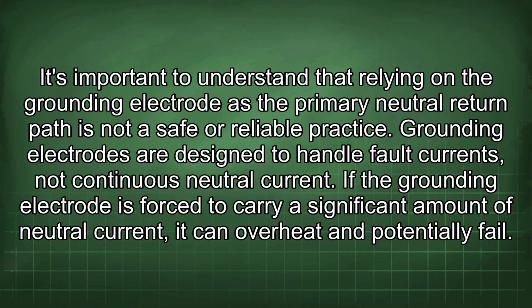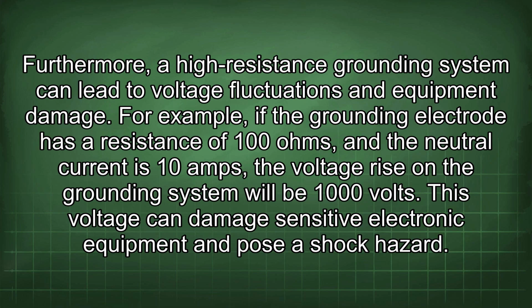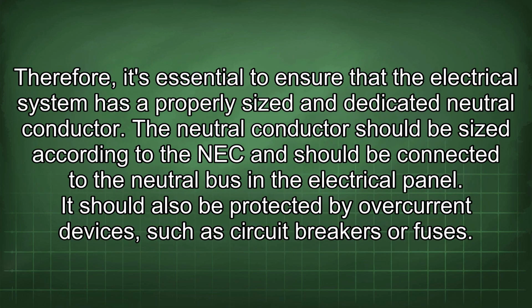If the grounding electrode is forced to carry a significant amount of neutral current, it can overheat and potentially fail. Furthermore, a high-resistance grounding system can lead to voltage fluctuations and equipment damage. For example, if the grounding electrode has a resistance of 100 ohms and the neutral current is 10 amps, the voltage rise in the grounding system will be 1000 volts. This voltage can damage sensitive electronic equipment and pose a shock hazard. Therefore, it's essential to ensure that the electrical system has a properly sized and dedicated neutral conductor.